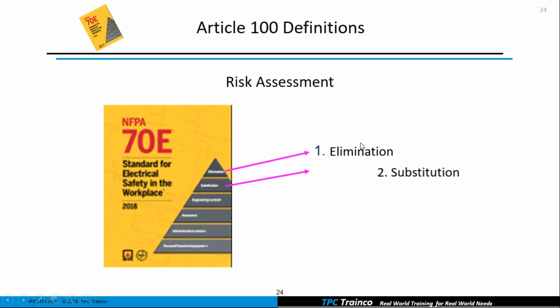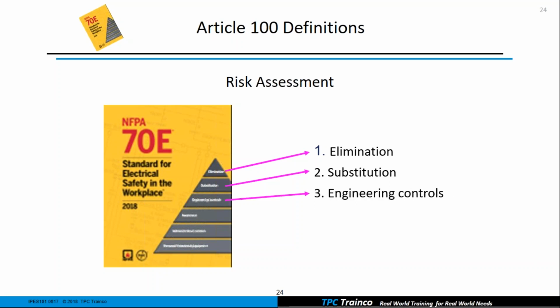And then we'll see number 2, substitution. So a good example of substitution would be that meter that we permanently install in our equipment. So I'm not going to have my workers go in there and test for a voltage and verify it's de-energized. I've substituted a different method. I've put in a meter there that's there all the time. And then we have engineering controls. The example I like to use here is if we have a worker that might go in and reset an overload once in a while, and they have to open the door up and reach in and press that overload. Well, maybe we can just relocate that overload to the outside of the equipment so that they don't have to open anything up at all.